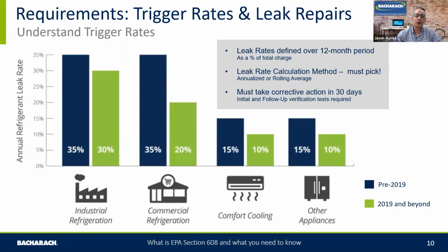So I'll use the analogy I just said before. You have a refrigeration system with 100 pounds of refrigerant in. You add 50 pounds in a 12-month period, that system would have a 50% leak rate. And it's important that you understand how the leak rate is calculated, because it's a pivotal and defining element of the EPA reporting. And also under EPA 608, you must define the calculation method.